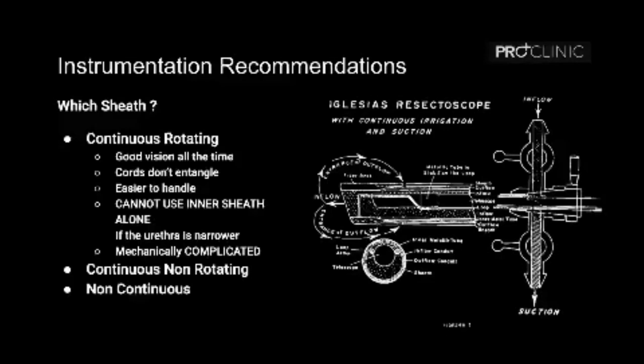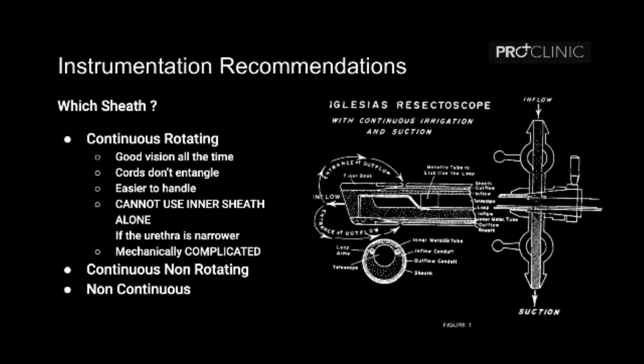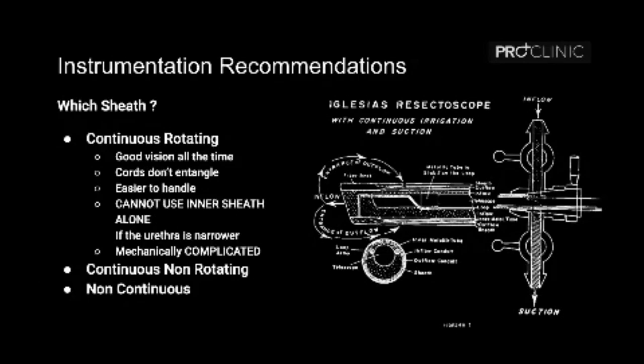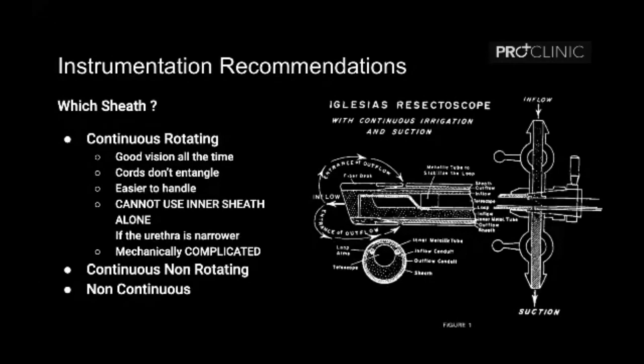Going back to the presentation: the advantage of the continuous rotating sheath is good vision at all times and cords don't entangle — it's easier to handle. But there is a disadvantage: the inner sheath does not have any inlet or outlet, so if the urethra is narrower you cannot use the inner sheath alone as a non-continuous resectoscope. In the older non-rotating version, you still had the option of using just the inner sheath — performing the resection by allowing water to go in and cutting, then removing chips subsequently.